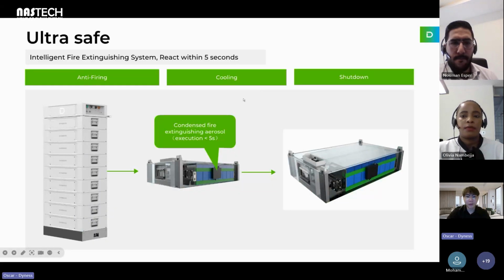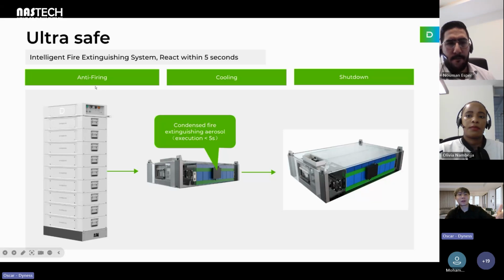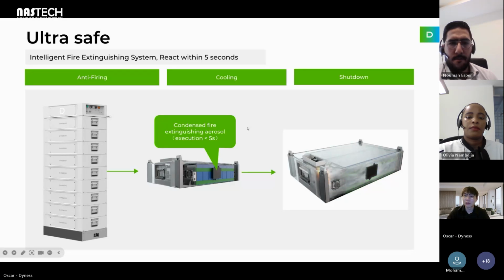Also for high voltage and commercial industrial solutions, and for these projects, people care about safety. Inside our battery, we have an integrated aerosol extinguisher, and we also integrated temperature and gas sensors. So when there is a fire, or some abnormal gas is generated, within 5 seconds our extinguisher will be triggered, taking off all the oxygen possible to put out the fire.